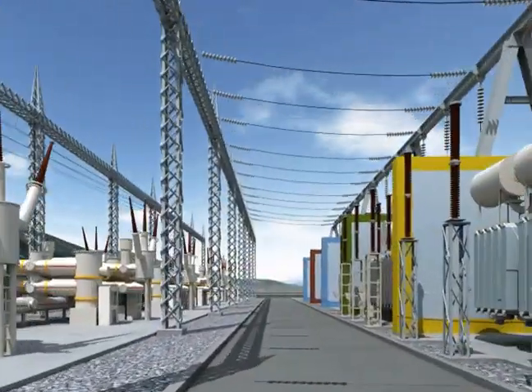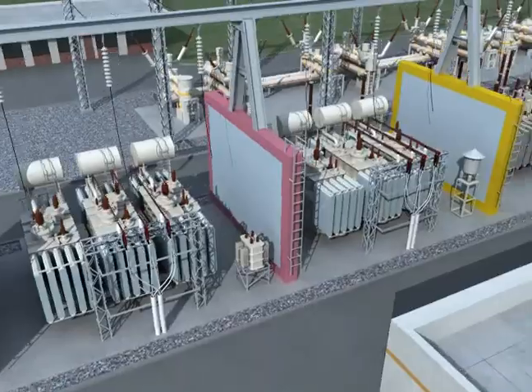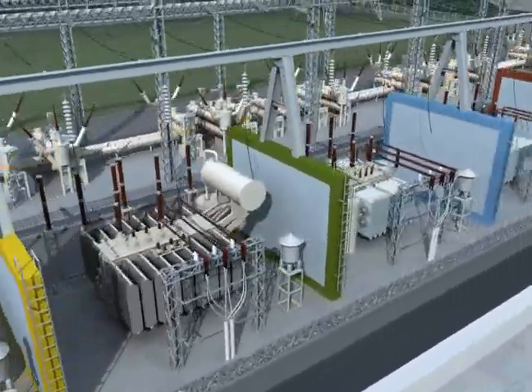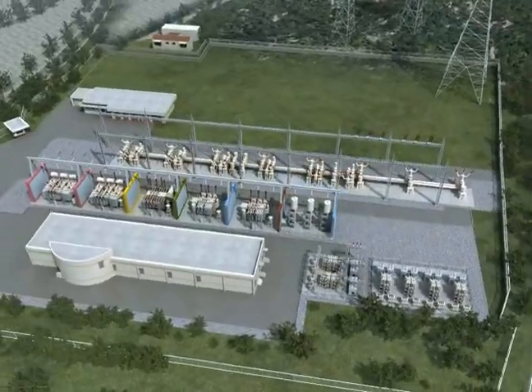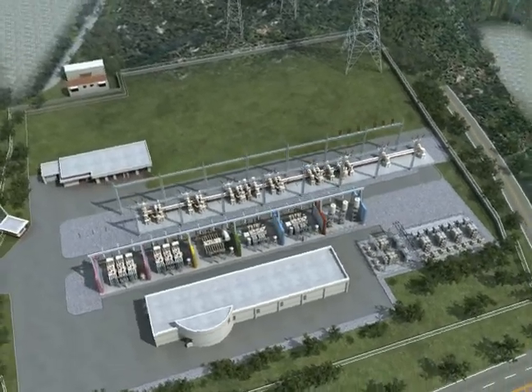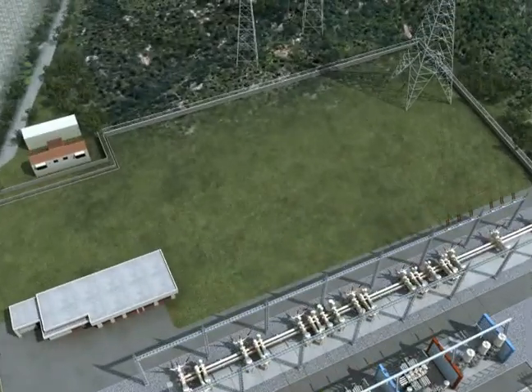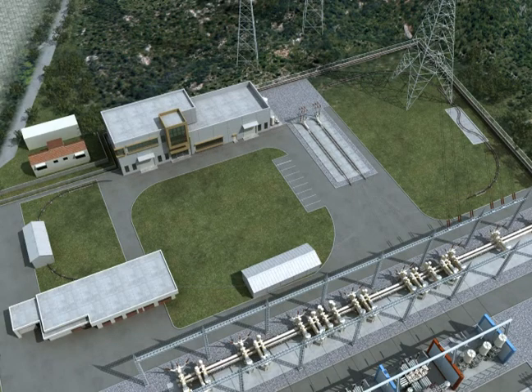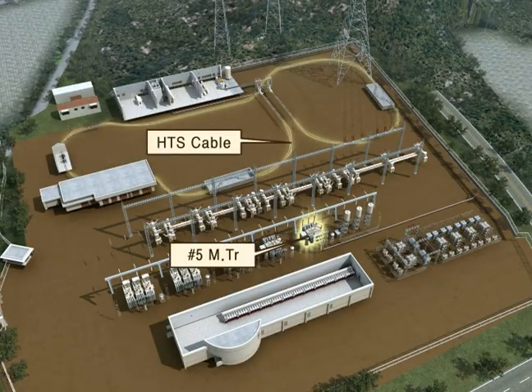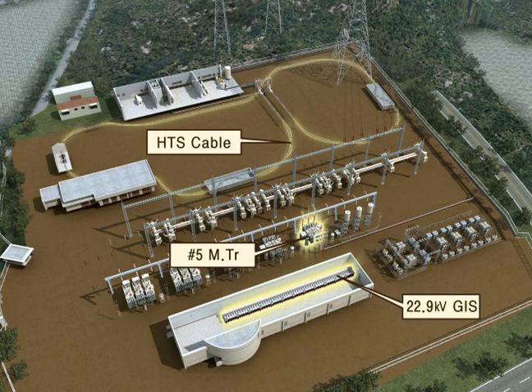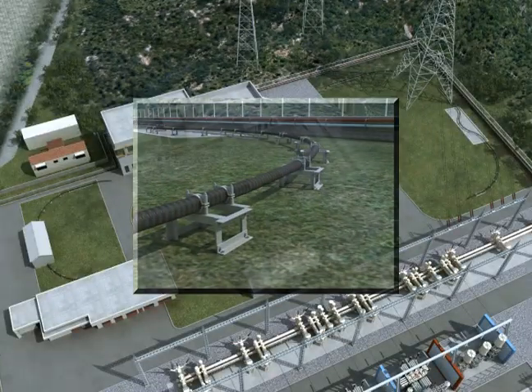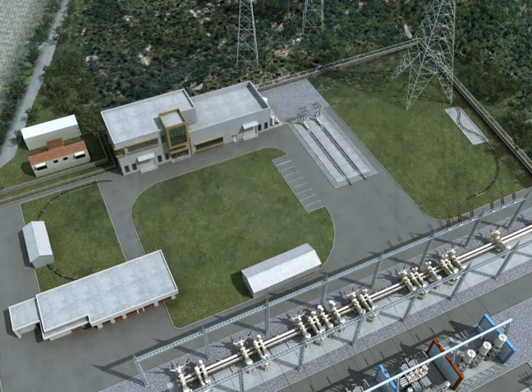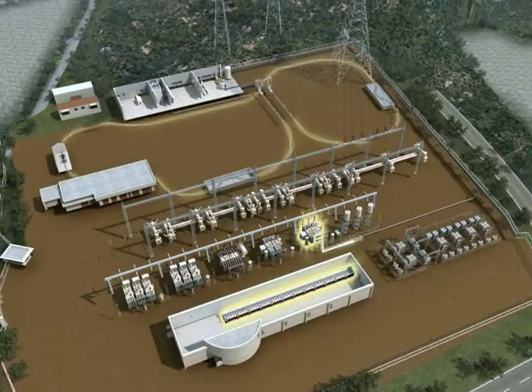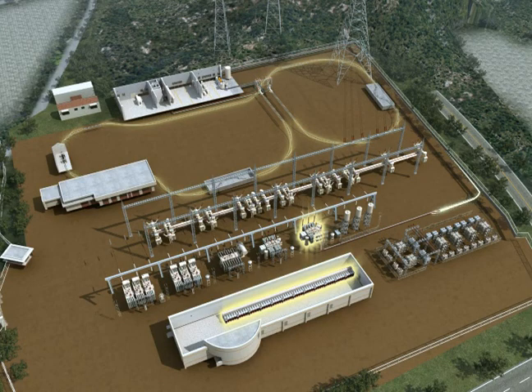The site for real grid installation and length of operation is decided to be at 154 kilovolts at the Ichon substation, considering the space, load condition, accessibility, etc. A superconducting cable system of 22.9 kilovolt, 50 megavolt ampere is installed between the number 5 main transformer and the 22.9 kilovolt line, which consists of an above-ground, duct, and offset section to mock actual site conditions.